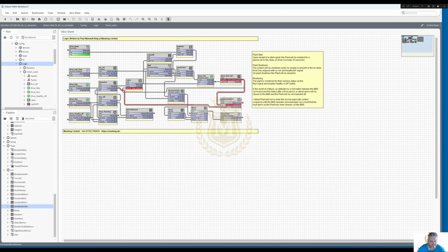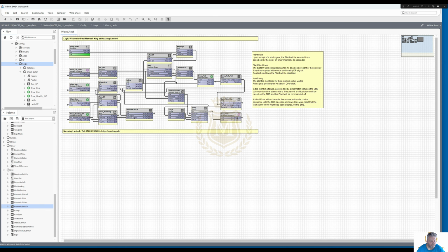And this is the fail now, because that system has failed. We've latched now the true signal there. We've latched it in the system, and basically we can't start without doing a reset. So let's put everything back to how it was. Emergency auto. Again, it still won't start. We need to do a reset. Now it's started. Now that will carry on running with no issue whatsoever.